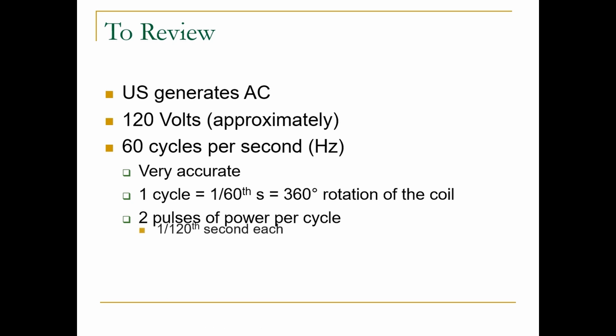Each pulse lasts for 1/120th of a second, half the rotation of the generator's coil. These 120 pulses of power can explain the characteristic of an X-ray beam in a single-phase generator, and how some older machines measured exposure time.